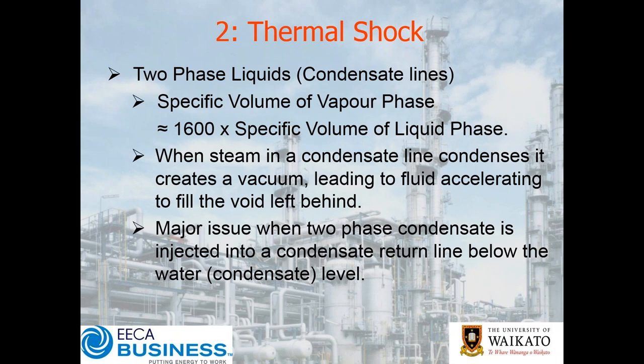When steam in a condensate line condenses, it will also create a vacuum. As the vapor is condensed, you get the reverse of the explosion — an implosion. We create a very localized vacuum effect which has to be filled by either liquid or more vapor, so you end up with a void which causes an acceleration of fluid. When that fluid is accelerating very rapidly and then hits a solid object, you get a bang — otherwise known as water hammer. This is a major issue when two-phase condensate is being injected into a condensate return line below the water level, because steam coming through will flash off some of that condensate and you get a percolator effect.